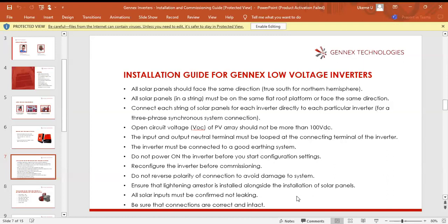All solar input must be confirmed not leaking. It may be leaking to ground, for instance, if after installation the frame of the rail is allowed to rest on cables and press them against the roofing sheets. There could be leakage. We are talking of high voltage here. Even when it's low voltage, the same thing is applicable. So ensure that there is no leakage by carrying out a PV test on the input solar connection. Be sure that the connections are correct and intact. After installation, you check all your terminals, breakers, polarities, and everything before you start switching on breakers.